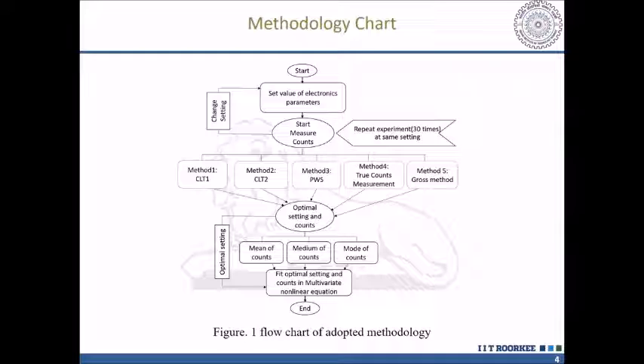Five different methods are used: central limit theorem first, central limit theorem second, pulse width saturation method, true counts measurement method, and the gross method, to find the optimal settings and the corresponding counts. We take the mean, median, or mode of the counts array that we get from repeating the experiment 30 times, and the optimal settings are fitted into a multivariate nonlinear equation to find the parameters that have a major contribution in counts measurement.